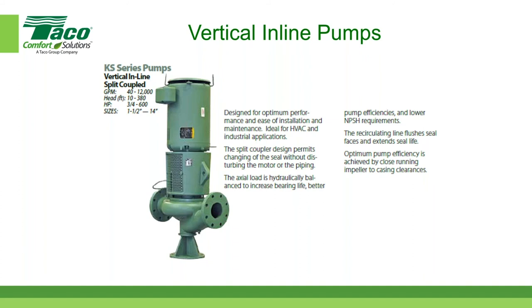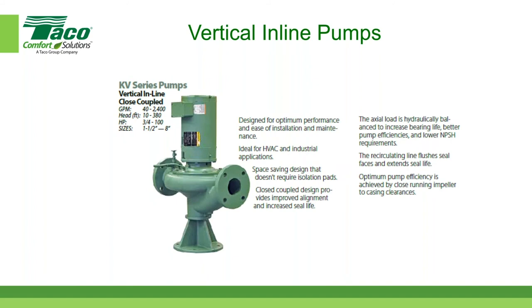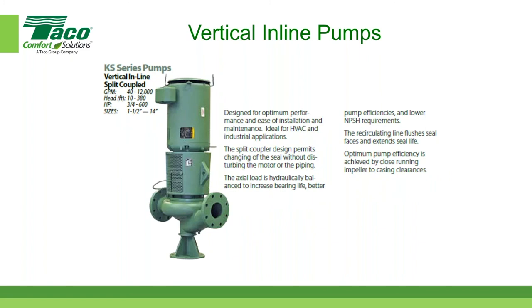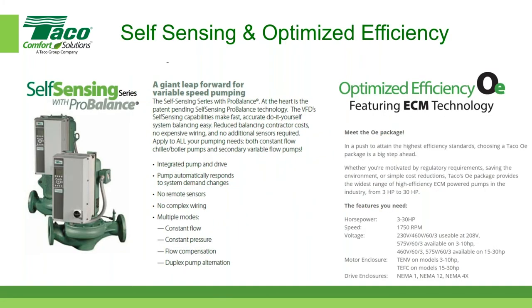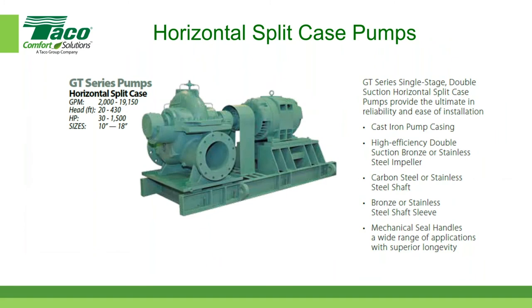Another popular vertical inline pump is the close-coupled pump, where the impeller is mounted directly on the motor shaft. A key difference with the KS model is that it allows you to remove a grill from the adapter and access the coupling inside, allowing you to service the seal without physically removing the electric motor. A lot of people like the KS model, especially at larger horsepower, because it's much more convenient for servicing. The next category is self-sensing pumps, which can be provided in both the vertical inline and the base-mounted end suction configurations.